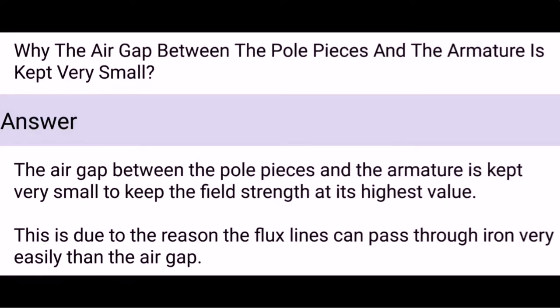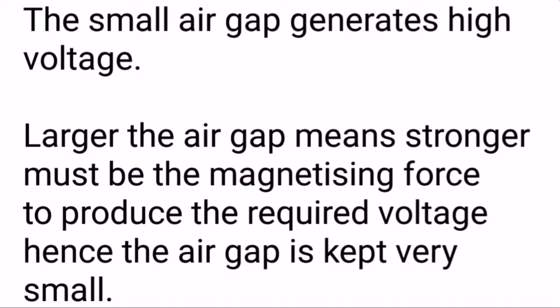Why is the air gap between the pole pieces and the armature kept very small? The air gap is kept very small to keep field strength at its highest value. This is because flux lines can pass through iron more easily than through air. A small air gap generates high voltage, whereas a larger air gap means a stronger magnetizing force is needed to produce the required voltage. Hence, the air gap is kept very small.